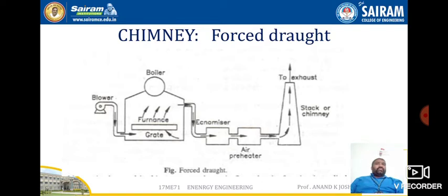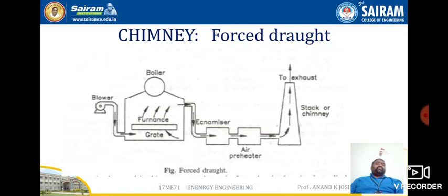In the forced draft arrangement, the blower is placed at the bottom of the grate with the furnace above. Once steam is generated, the economizer and air preheater are used, and the flue gas is discharged through the stack or chimney. The function of the chimney here is to discharge gases high into the atmosphere to prevent contamination. It is not significant for producing draft, so the chimney height does not need to be very tall in a forced draft system.